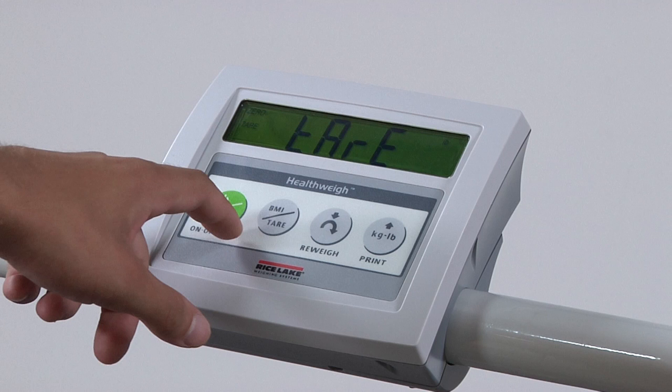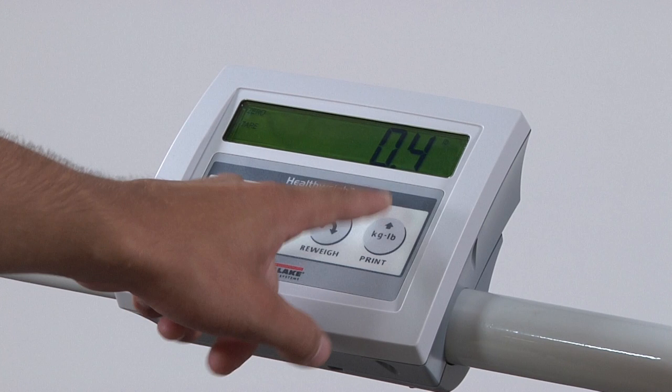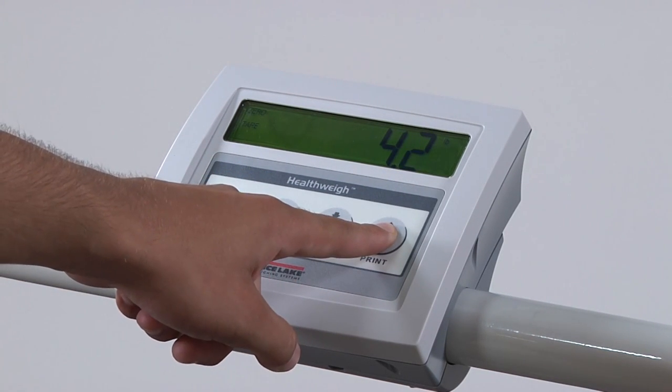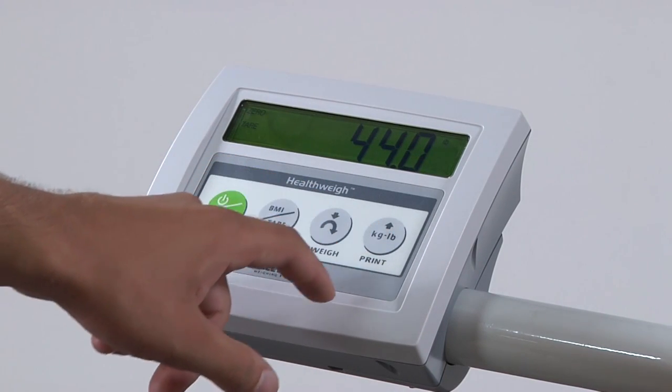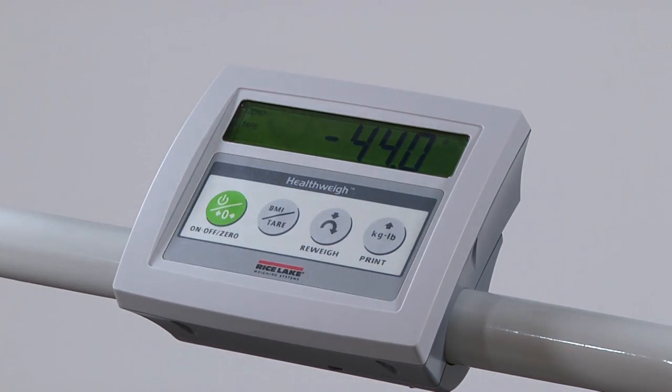To change your value, press and hold the pound/kg key until the furthest digit to the right represents the first number of your tare value. For example, to enter 44 pounds, hold the pound/kg key until the first digit reads 4. To enter the next digit, quickly press the pound/kg key twice and hold until the next value is reached. When your complete value is entered, press the tare key once more. You may now accurately weigh the patient.